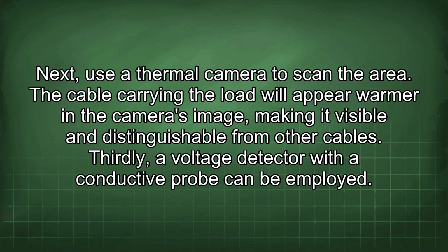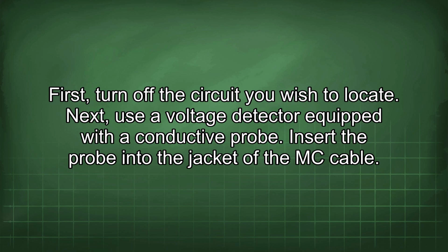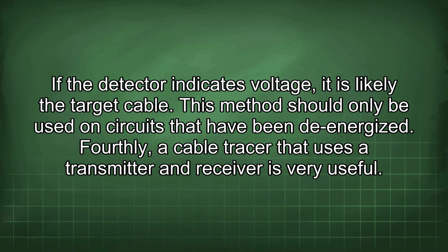Thirdly, a voltage detector with a conductive probe can be employed. First, turn off the circuit you wish to locate. Next, use a voltage detector equipped with a conductive probe. Insert the probe into the jacket of the MC cable. If the detector indicates voltage, this is likely the target cable. This method should only be used on circuits that have been de-energized.